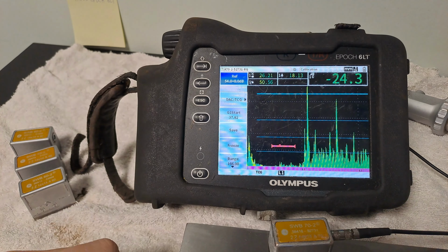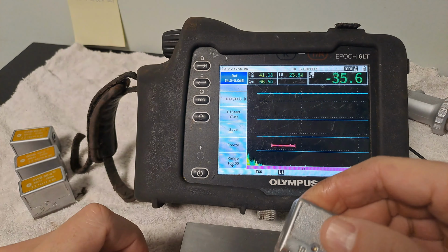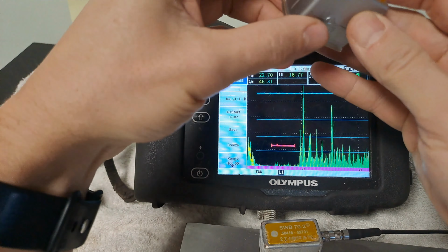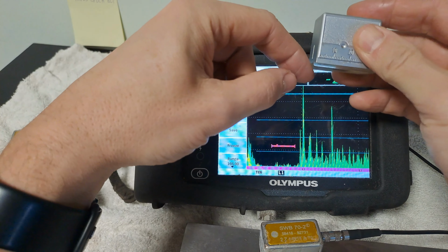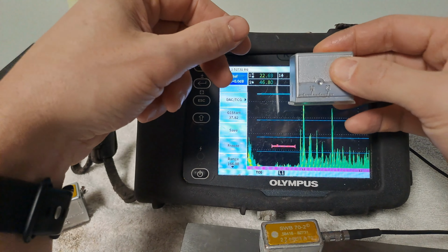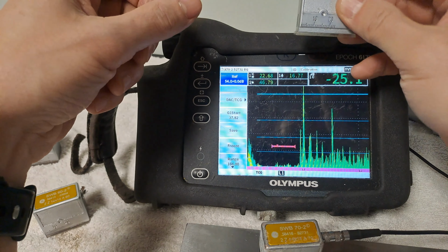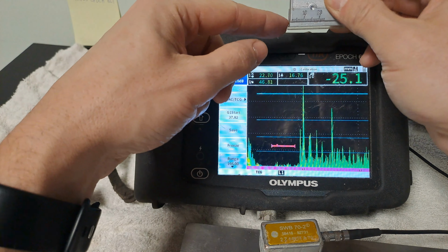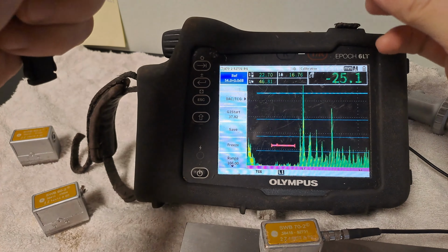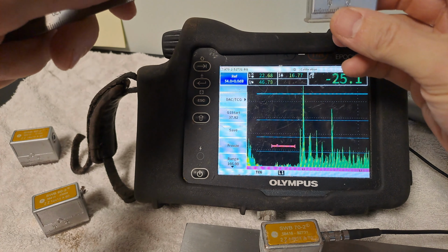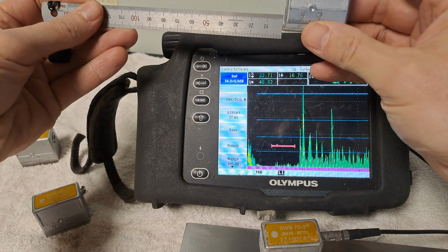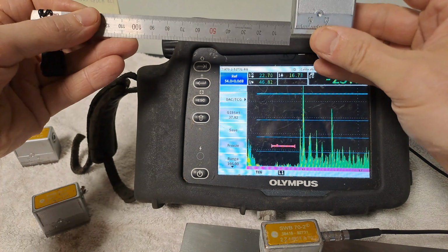And another thing that I want to tell you is, I have found here this one that I have, that's not perfect. I cannot see here, it's not in the beginning. So if you have such a probe with a pad glued, and when you measure you put your ruler down here, it will be off because there is a gap there.